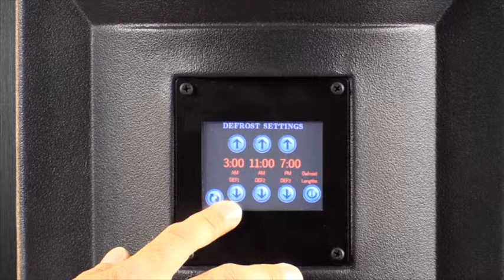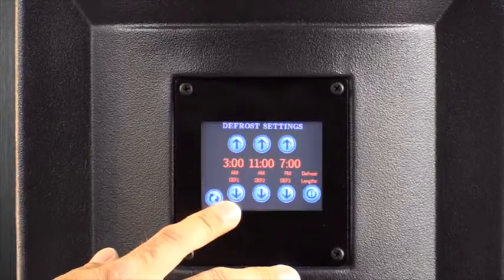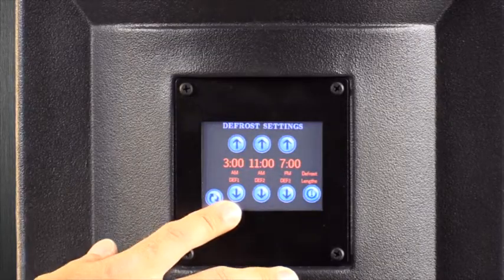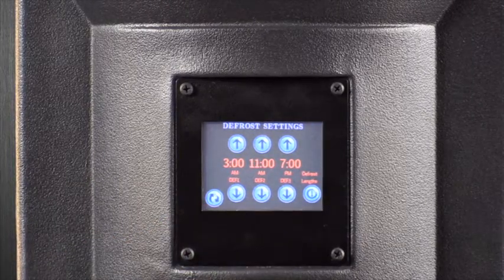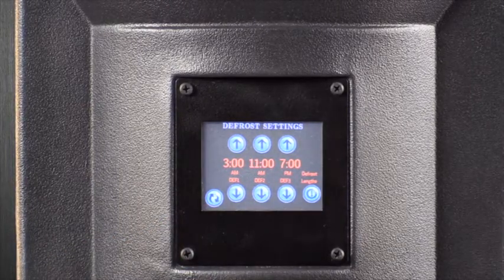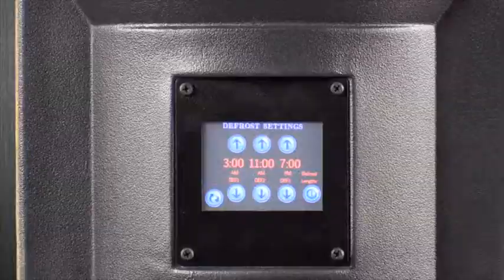The unit is programmed to go into its defrost cycle 3 times a day, every 8 hours, which are at 3 a.m., 11 a.m., and 7 p.m. Defrost settings. This screen will show the 3 different time durations in minutes for each defrost cycle. These are all pre-programmed as a default on all units and are also not recommended to be changed or altered at any time.